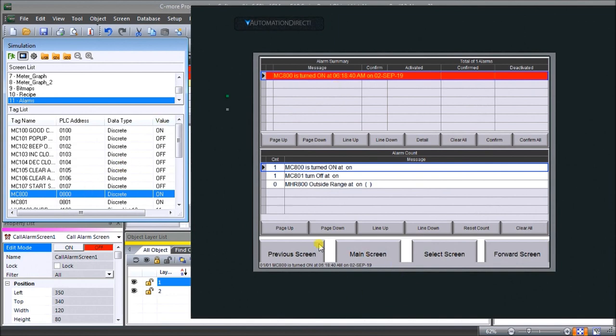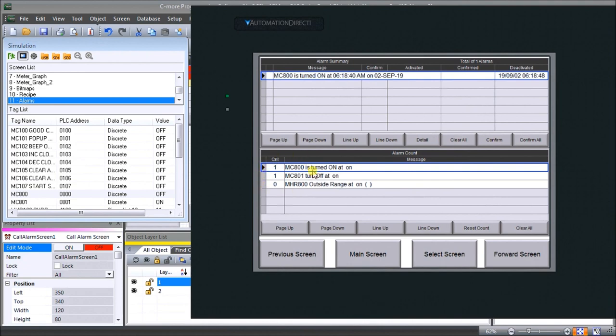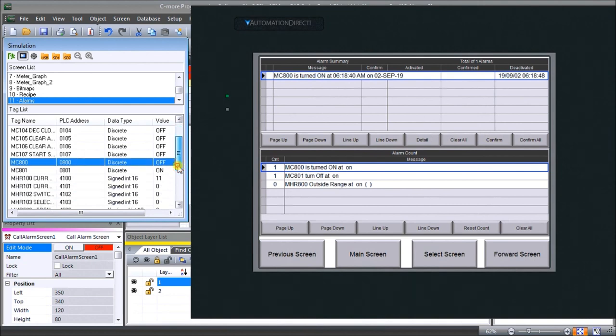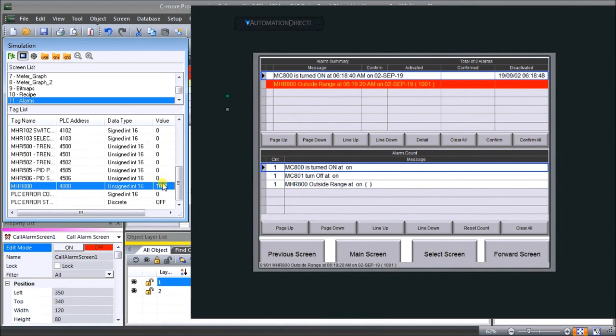Let's go to MC800 and turn it on — you can see it's turned on at this time. You can also see it at the bottom of the screen. Then we turn it off and it goes off. Because we didn't confirm it on the first one, it won't confirm when we hit the confirm button. On our history our count is now one of each. Then for MHR800, the value has to be between 0 and 1000 — let's put in 1001. When I hit enter, you'll see it's outside the range of 1000 that we specified, so it activates our alarm.